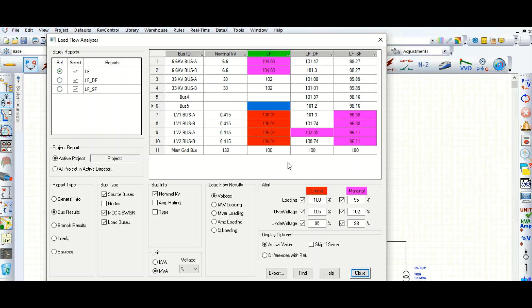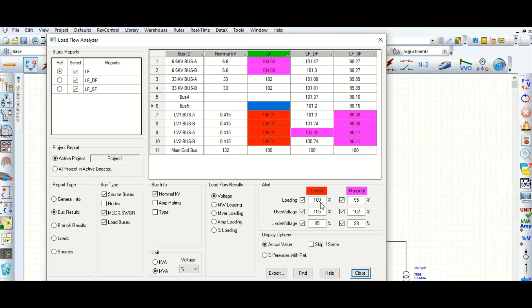If the loading is 95 percent, a marginal alert will appear in pink color. So this is loading in percentage — over-voltage shows in red and under-voltage is indicated similarly. In this way you can easily notice marginal alerts and critical alerts, and compare them all with the help of this Load Analyzer page.